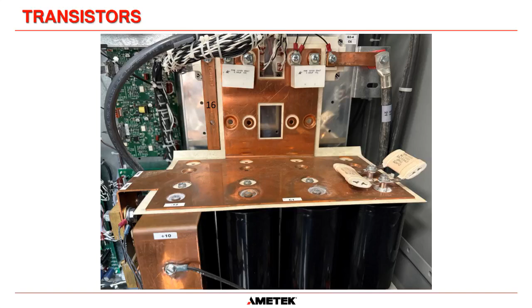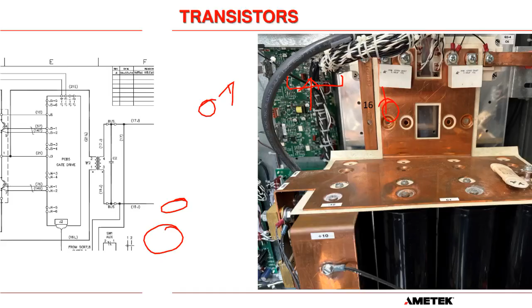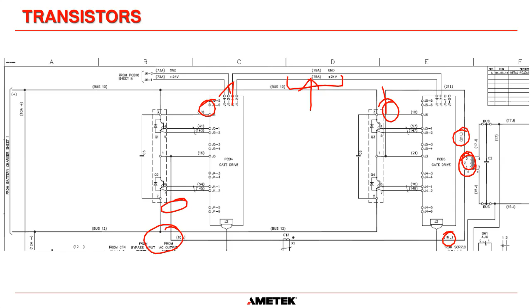This is what our bridge looks like. Number 10 is our positive going in, number 12 is our negative. Our IGBTs are up here behind these capacitors - you can see this white device, that's our IGBTs. We can see 21 and 16; going back here, 16 is the input to the transformer. So we've got positive and negative going in, and 21 and 16 going out - DC going in and AC out. That's as simple as the inverter bridge gets.